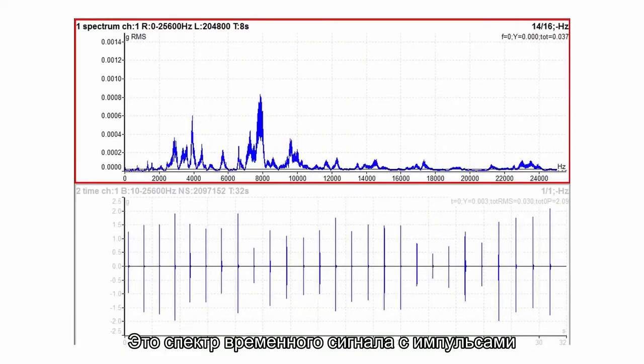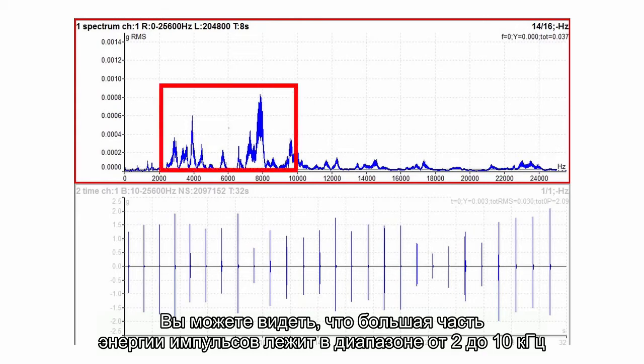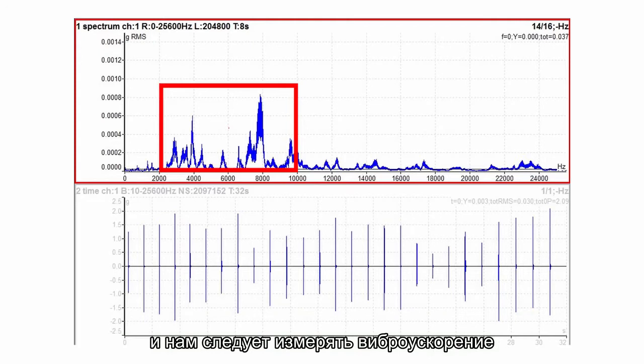This is the spectrum of time signal with shocks. You can see that most of the shock energy is from 2 to 10 kilohertz. It means that the accelerometer must measure in this frequency range and we should measure in acceleration.